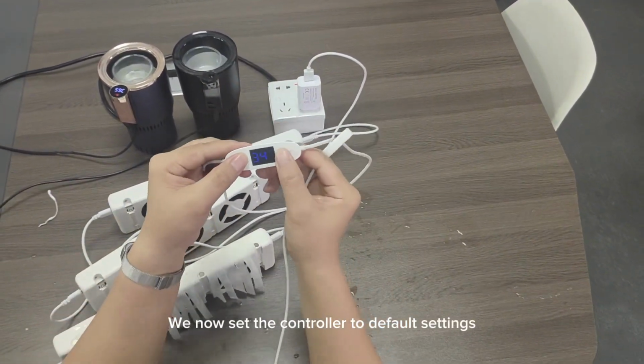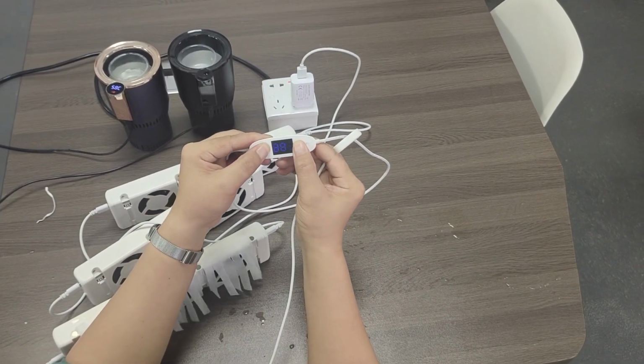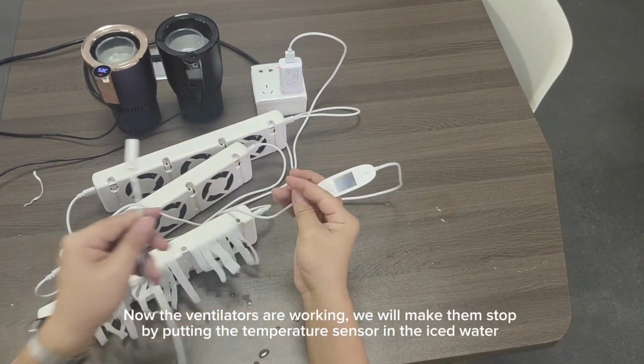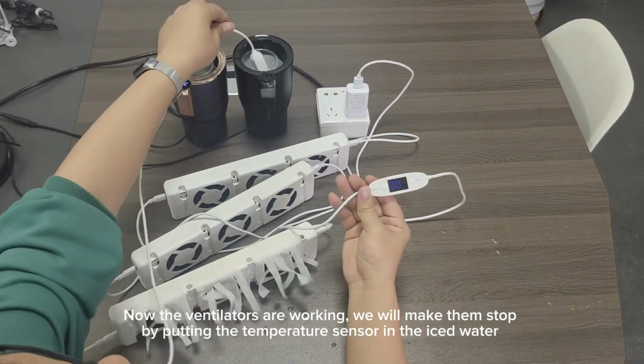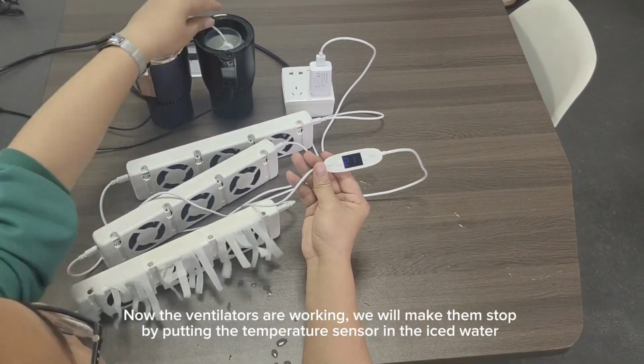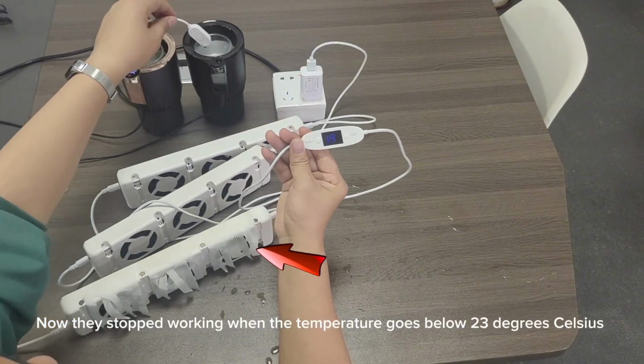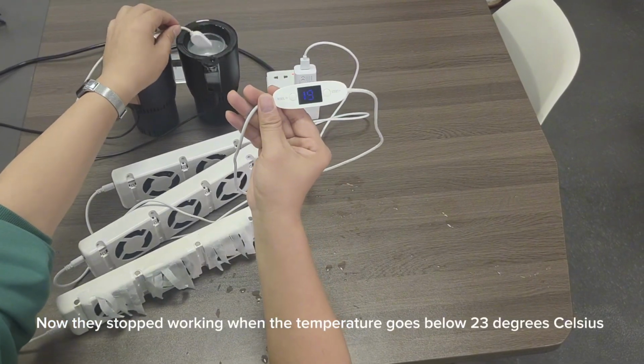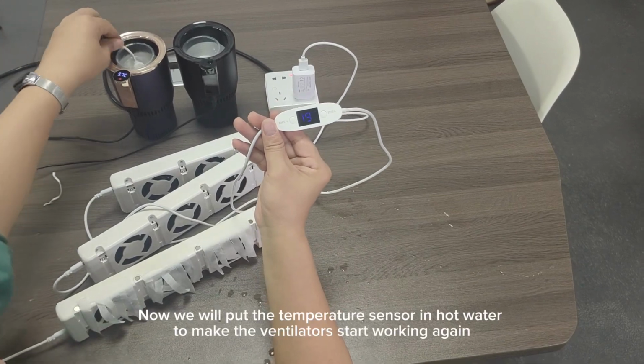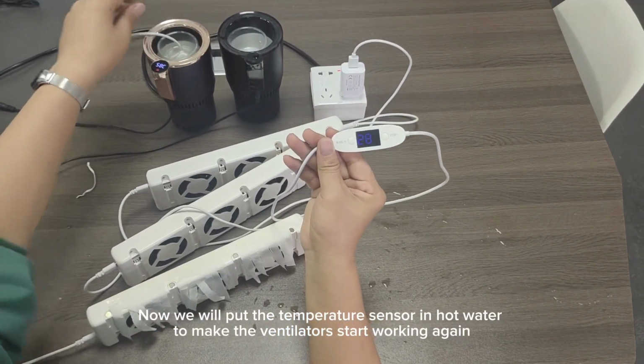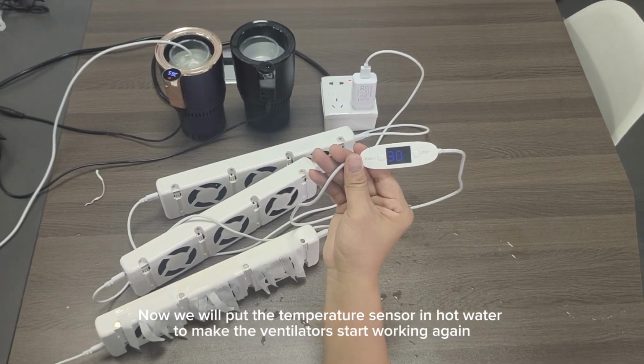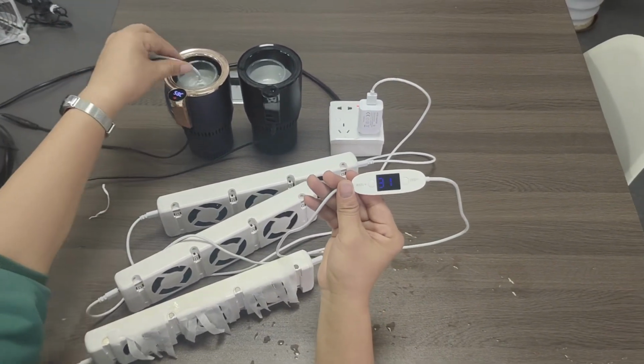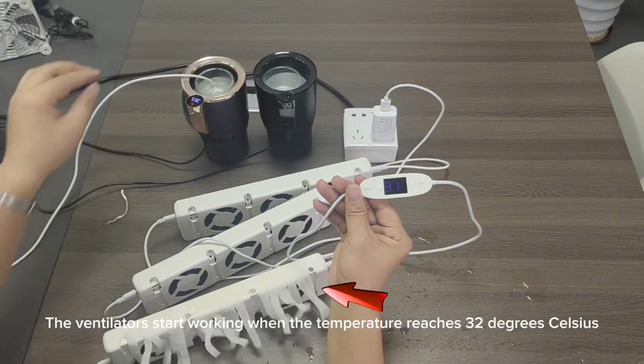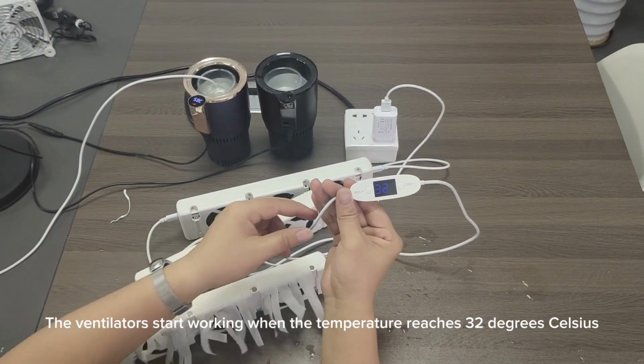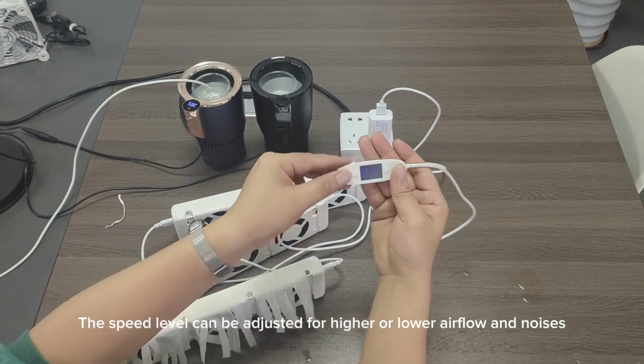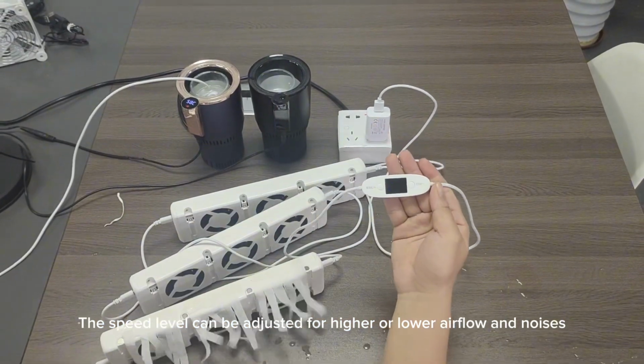We now set the controller to default settings. Now the ventilators are working. We will make them stop by putting the temperature sensor in the iced water. Now they stopped working when the temperature goes below 23 degrees Celsius. Now we will put the temperature sensor in hot water to make the ventilators start working again. The ventilators start working when the temperature reaches 32 degrees Celsius. The speed level can be adjusted for higher or lower airflow and noises.